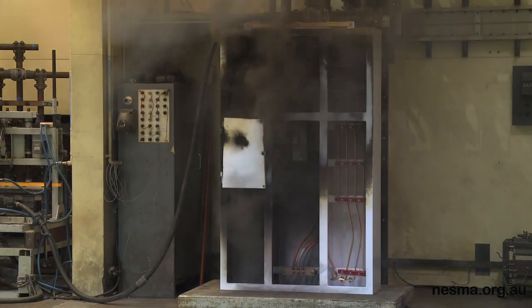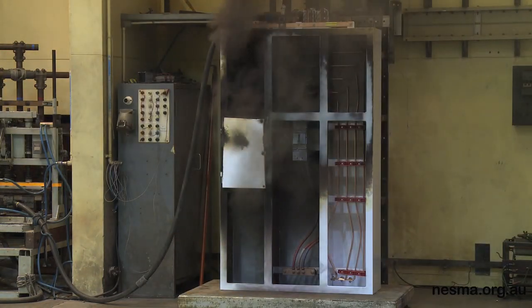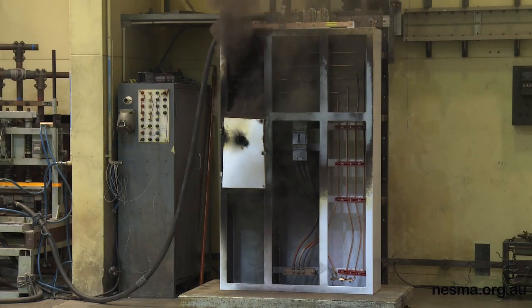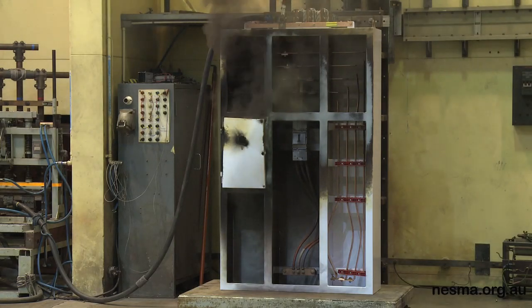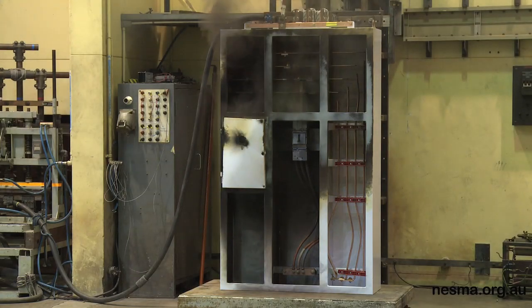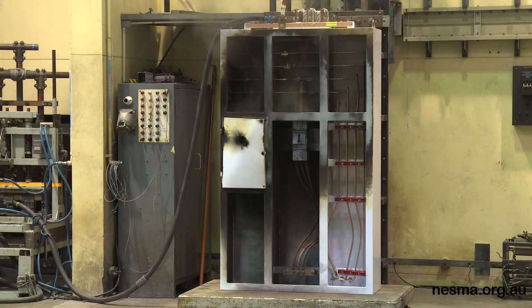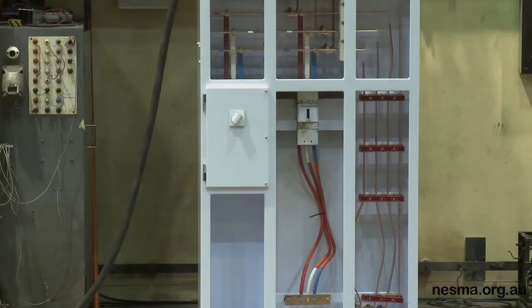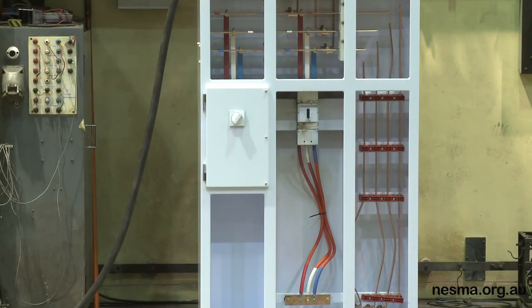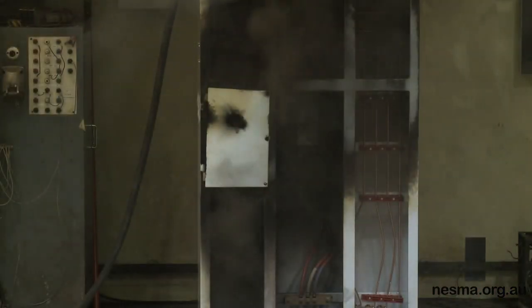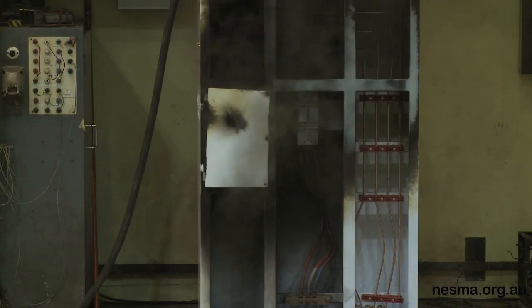One of the other assessments is that parts are ejected from the enclosure as well. So if you look at the 61641, they do a measurement of mass, and anything 60 grams or above that is projected towards the indicator or hits the indicator is deemed to be a hazard to an operator as well. So it's not only the flame, it's parts that might be ejected from the assembly during that test.